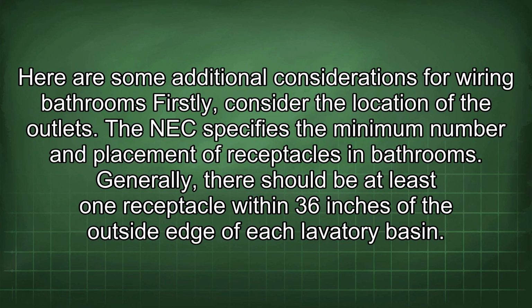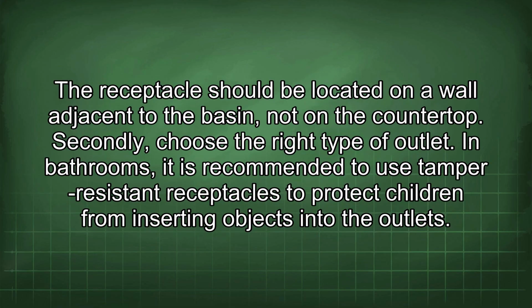Here are some additional considerations for wiring bathrooms. Firstly, consider the location of the outlets. The NEC specifies the minimum number and placement of receptacles in bathrooms. Generally, there should be at least one receptacle within 36 inches of the outside edge of each lavatory basin. The receptacle should be located on a wall adjacent to the basin, not on the countertop.